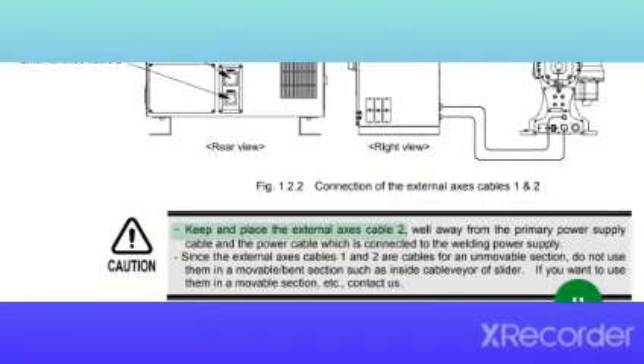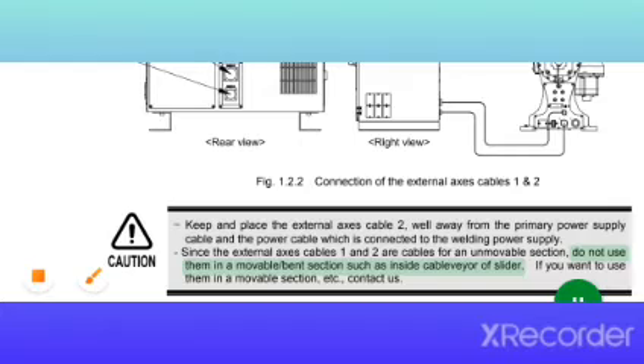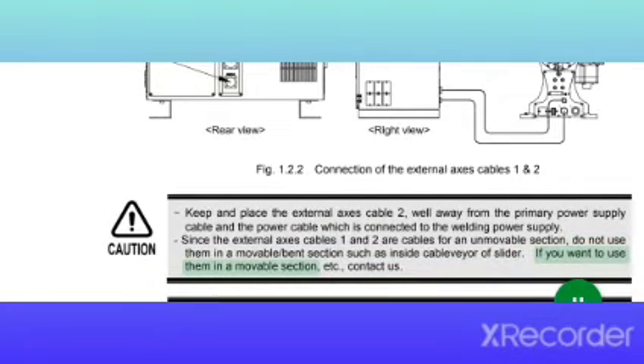Caution: keep and place the external axes cable 2 well away from the primary power supply cable and the power cable which is connected to the welding power supply. Since the external axes cables 1 and 2 are cables for an unmovable section, do not use them in a movable/bent section, such as inside cableveyor of slider. If you want to use them in a movable section, etc., contact us.